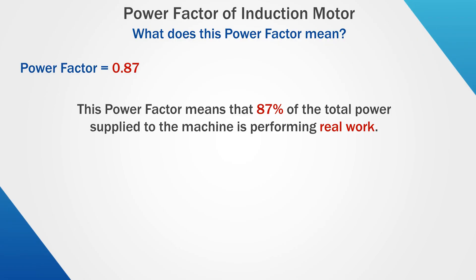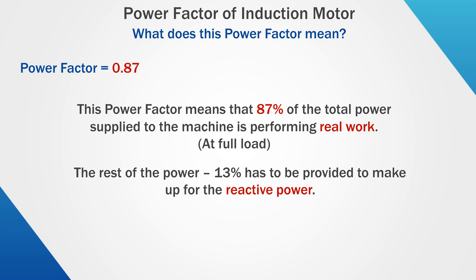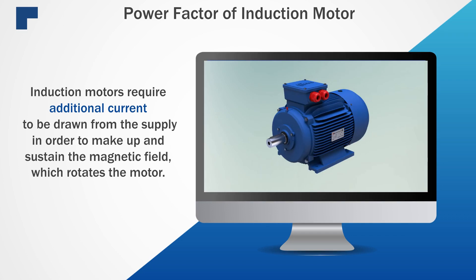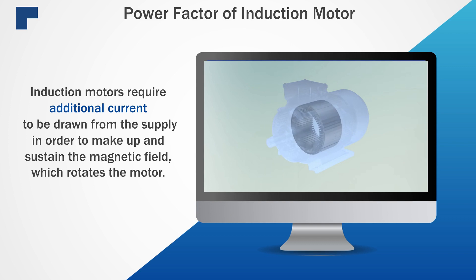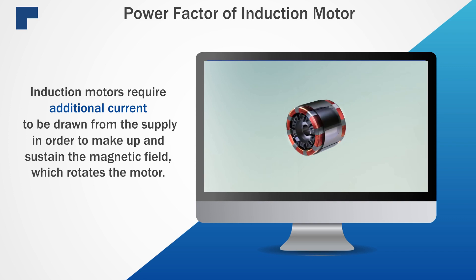This power factor means that 87% of the total power supplied to the machine is performing real work. The rest of the power, 13% to be exact, has to be provided to make up for the reactive power. Reactive power causes additional reactive current to flow across the installation. Like any other AC machine, an induction motor requires that additional current to be drawn from the supply in order to make up and sustain the magnetic field which rotates the motor.